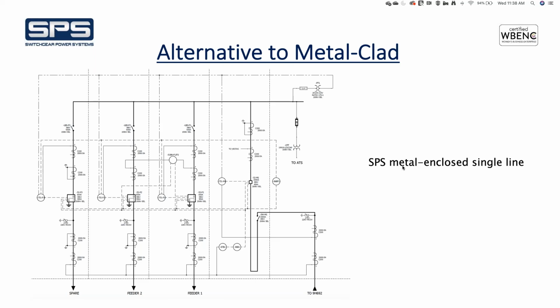Yeah, and so if there are cost concerns, for a substation that has maybe an incoming breaker and 3 feeders, I don't know exactly how big it is, you might consider utilizing the hybrid design where you could put the batteries and relay panels you need in the control room, integrated right in the non-walk-in switchgear. That could possibly save you having to buy a separate control house from somebody like Trachte.